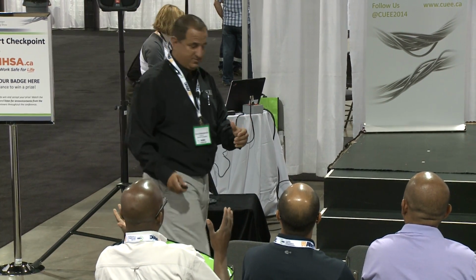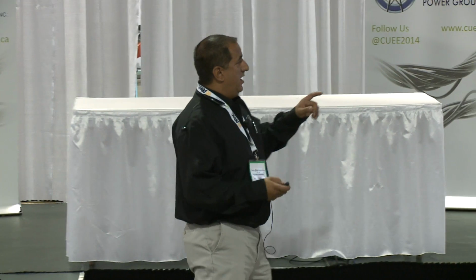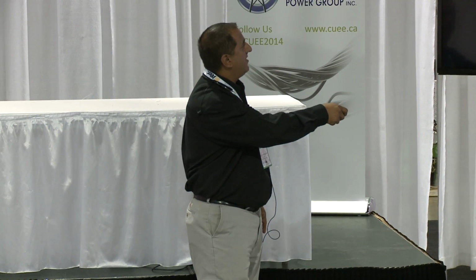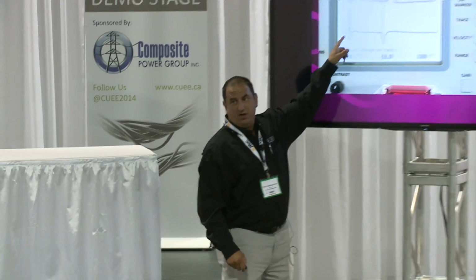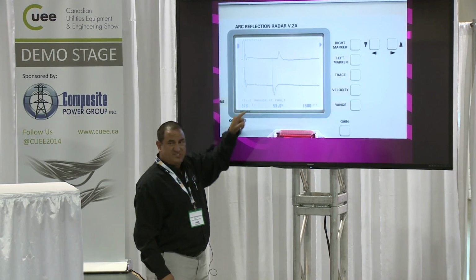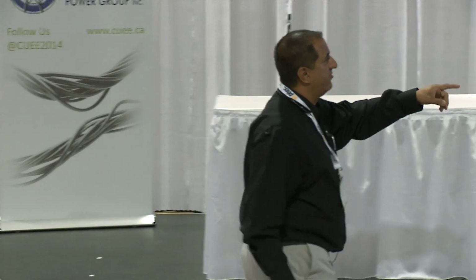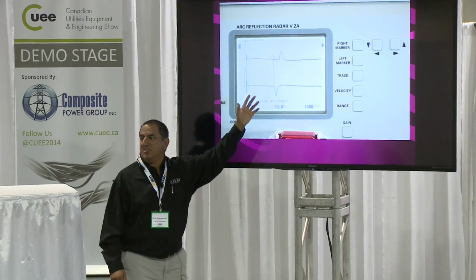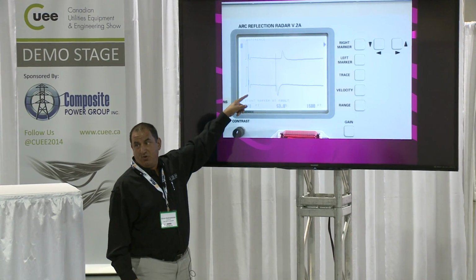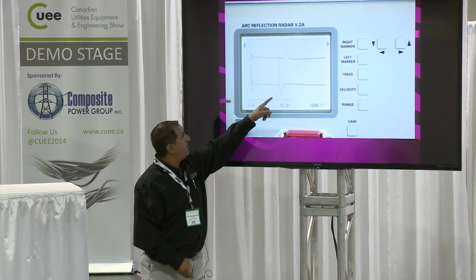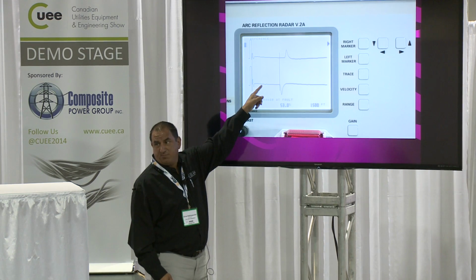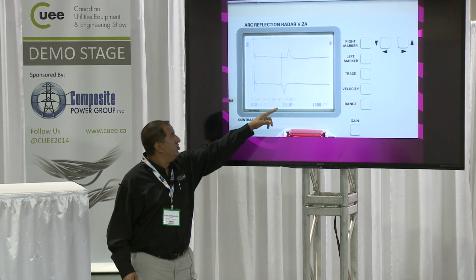If there's a splice on the cable, yes. This isn't a good picture of it. If you go back a few, okay. This is what we call the radar trace, right? In here, you would see a little S laid on its side. That would indicate that's what a splice is. So what this machine will pick up would be the end of your cable, the fault, a splice, or transformers. So what you would do is, if you said, okay, this really isn't a splice, but there is a change there, so let's just say that was the splice. This right here is my 0 point. This right here is wherever the fault is. If that was a splice right there, you hit that right marker button at the top, you move that marker to there, and it would say, okay, at 341 feet, that's where my splice is.